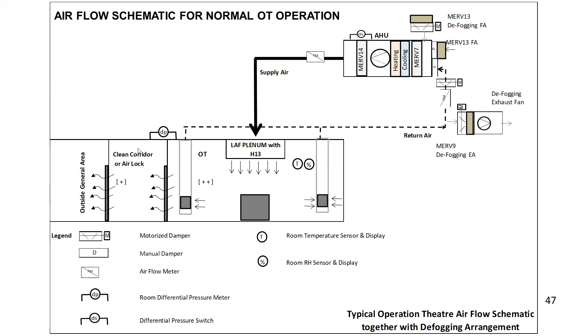It is observed by very few hospitals, but there are quite a few who are still observing it. That's why I showed this. So at the end of the day, after several operations, they would like to fog the operation theaters and keep it very clean from a microbial point of view, so that the next day you start all over again. So you have to have this fogging and defogging arrangement, which works on timers. And you can see that this area is under positive pressure. Then they've got the airlock, which is under less positive, and then it goes into the outside general area. But when the same thing is to be done for COVID times, then what we want is that this air from the operation theater should not go into the outside general area.